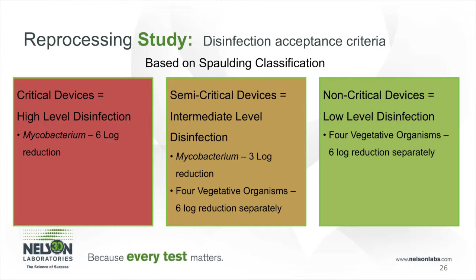The testing for disinfection is based on Spaulding classification, and this specifies that all critical devices have to go through a high-level disinfection process, and the acceptance criteria for this test is a 6-log reduction of a Mycobacterium species. For semi-critical devices, these devices need to go through an intermediate level disinfection, and the acceptance criteria for this type of disinfection is a 3-log reduction of the Mycobacterium species and a 6-log reduction separately of 4 vegetative organisms. And these are Klebsiella pneumoniae, Escherichia coli, Staphylococcus aureus, and Pseudomonas aeruginosa. For non-critical devices, this requires a low-level disinfection and requires a 6-log reduction of the 4 vegetative bacteria that I just mentioned.